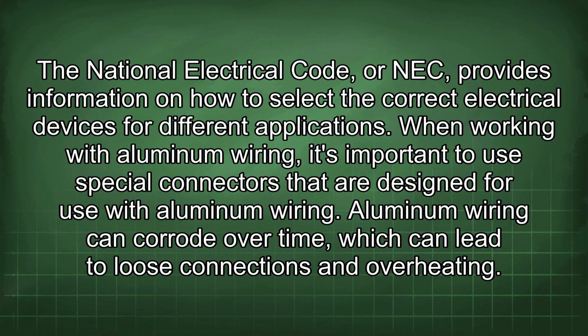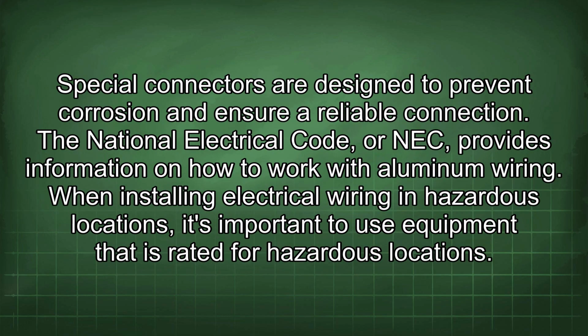When working with aluminum wiring, it's important to use special connectors that are designed for use with aluminum wiring. Aluminum wiring can corrode over time, which can lead to loose connections and overheating. Special connectors are designed to prevent corrosion and ensure a reliable connection. The National Electrical Code, or NEC, provides information on how to work with aluminum wiring.